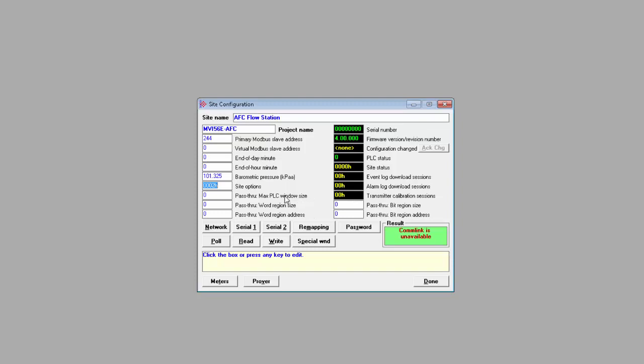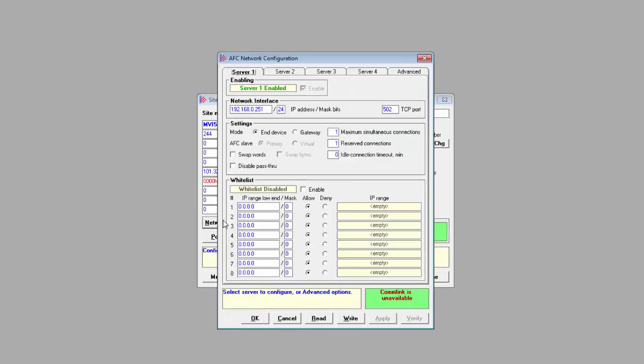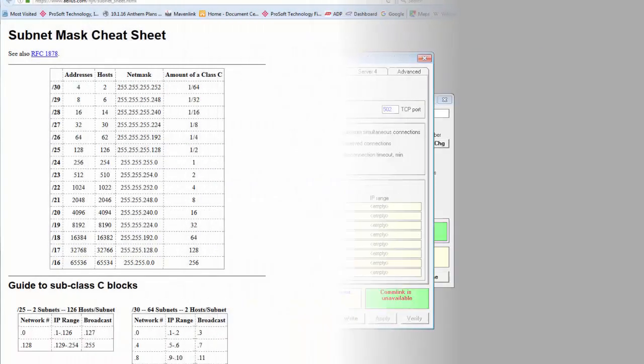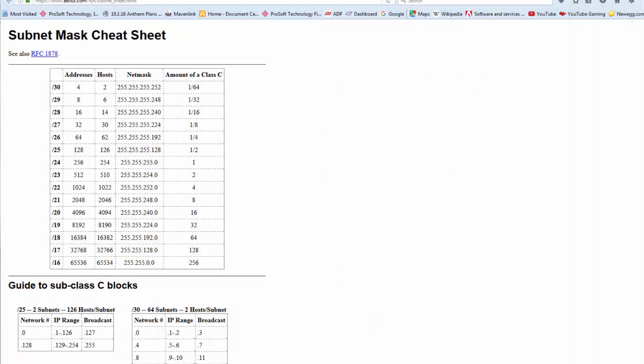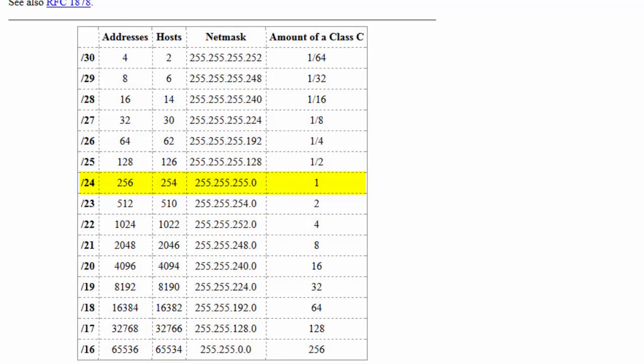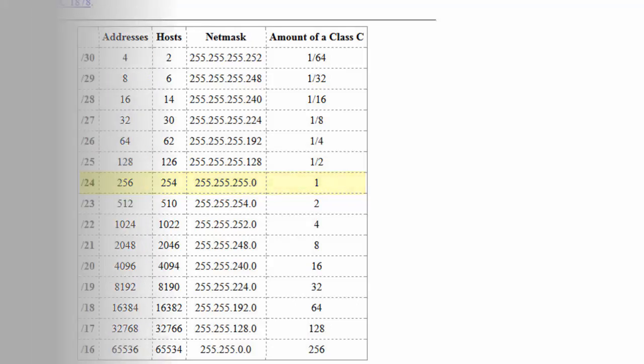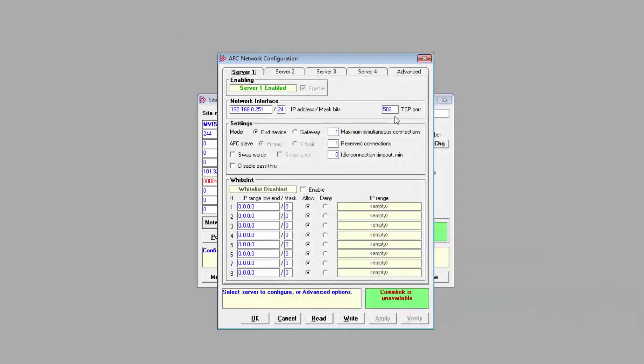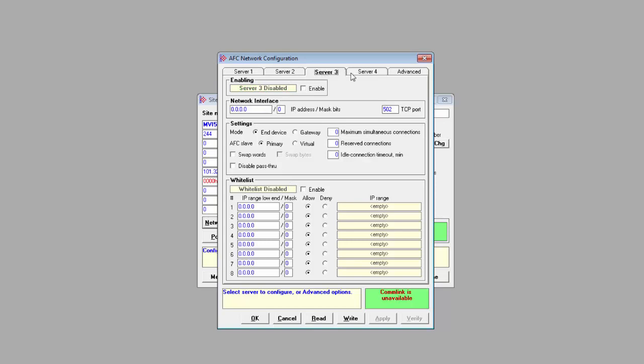There is also barometric pressure and site options and pass-through settings. The next thing to do is to set our communication parameters. The Network, Serial 1, and 2 buttons allow you to configure the setting for each of those ports. We'll click the Network button, which opens the configuration window for the Modbus TCP port. This is where you can enter the IP address that you want the AFC module to use in your application. Now we'll need to connect via its default IP address of 192.168.0.251 for the initial download, so we'll leave it at the default for now. Mask bits indicate the network prefix length of the physical interface. 24 bits is the equivalent of the typical 255.255.255.0 network mask.